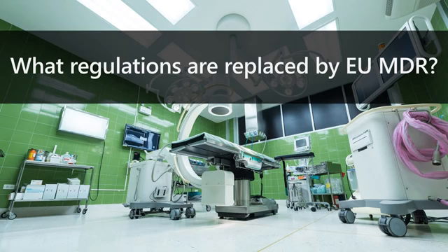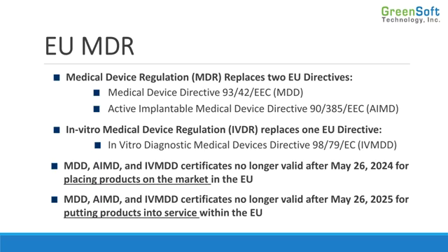So when we look at the MDR, we have the timeline, but how does it relate to the existing regulations we're currently working with? Well, companies that make medical devices right now are probably working with either the Medical Device Directive or the Active Implantable Medical Device Directive, depending on what type of product it is. Now, the MDR is going to replace both of these. So regardless of which directive you're using, you're going to have to move to the new MDR moving forward. The IVDR, which is the one that comes into effect 2 years later, is replacing the In Vitro Diagnostic Medical Devices Directive. So it's basically replacing a previous version of itself.